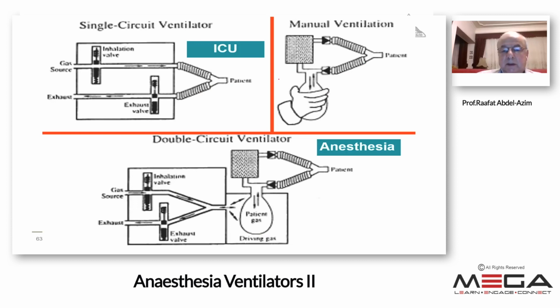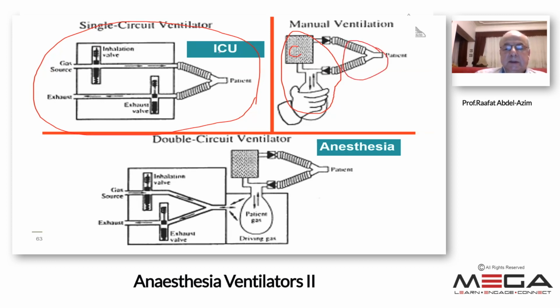Another classification: this is the anesthesia ventilators here, down. The upper one is the ICU ventilator here. In the ICU ventilator, there is no breathing circuit including the bellows and reservoir bag. So no bellows and no reservoir bag. This circuit is here also. So combining the circuit on the right side up with the ICU ventilator on the left side gives the anesthesia ventilators that we call double circuit. Why do we call it double circuit? Because there is a circuit inside the ventilator and a circuit outside the ventilator, that is the breathing circuit, so it is called double circuit.